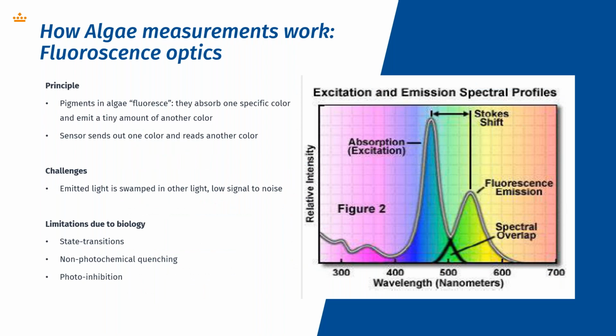If we look at how algae measurements work, it works with fluorescence optics. The principle is quite easy. The pigments in algae fluoresce. They absorb one specific color and emit a tiny amount of another color. This is shown in the graph you see here on the right side. It's telling us about excitation and emission spectral profiles. When a sensor is beaming light on algae, there is a certain absorption, also called the excitation of the algae pigment, and they send a fluorescence emission back, and that is what the sensor gets back and translates into an algae concentration or fluorescence units. The sensor sends out one color, as said, and reads another color.